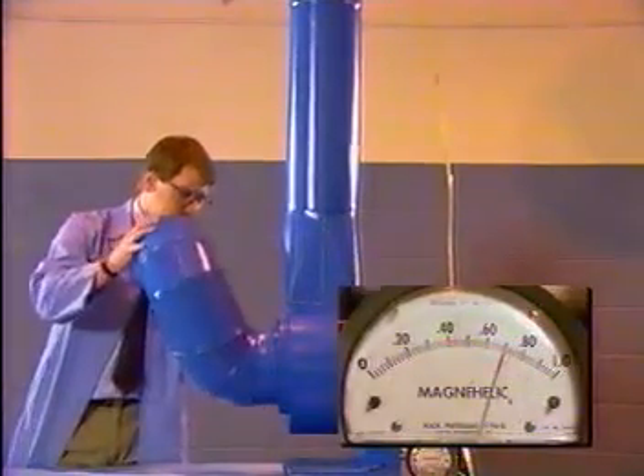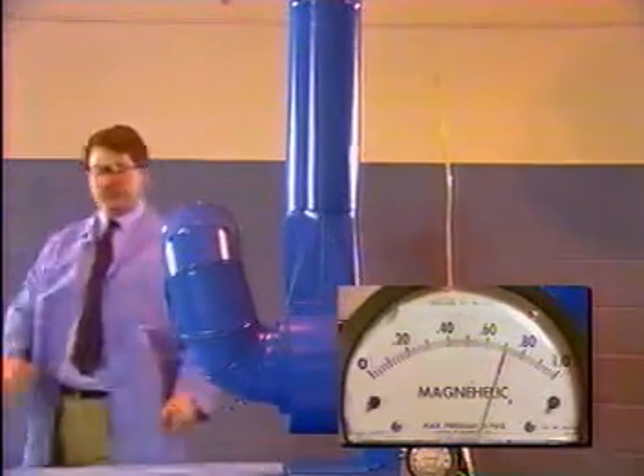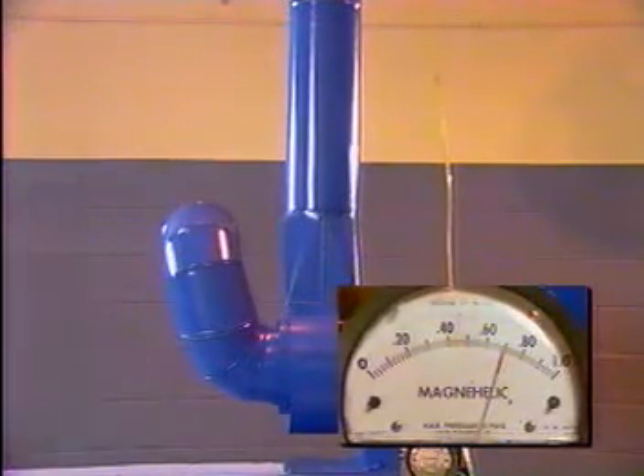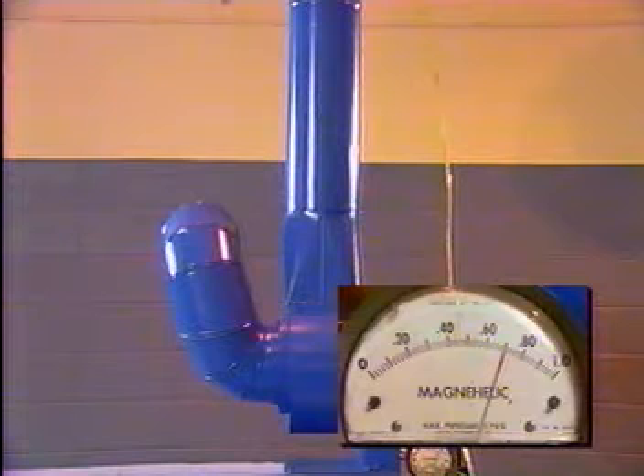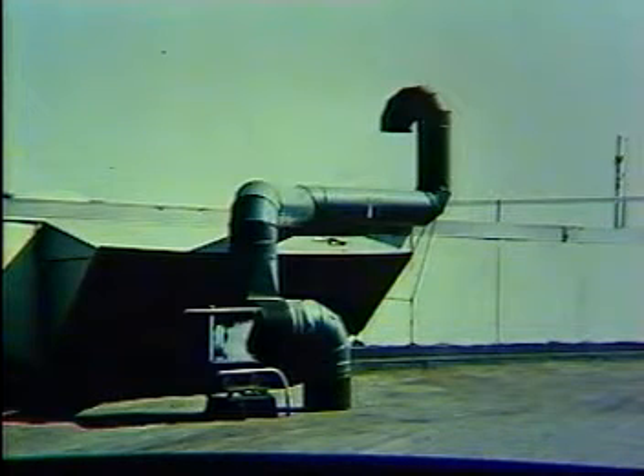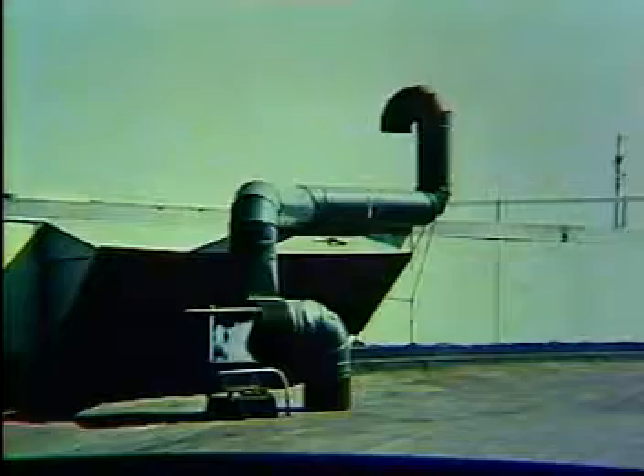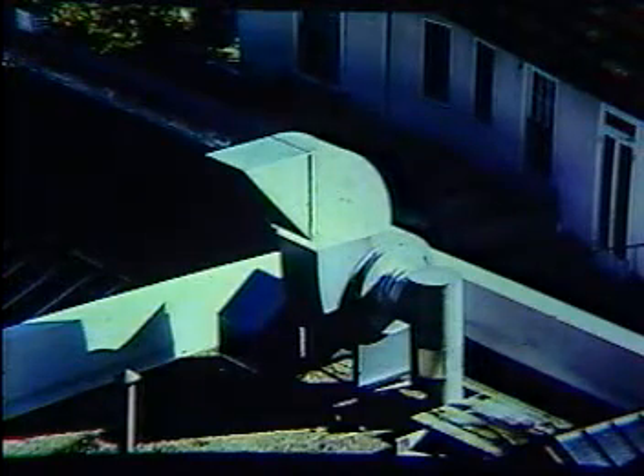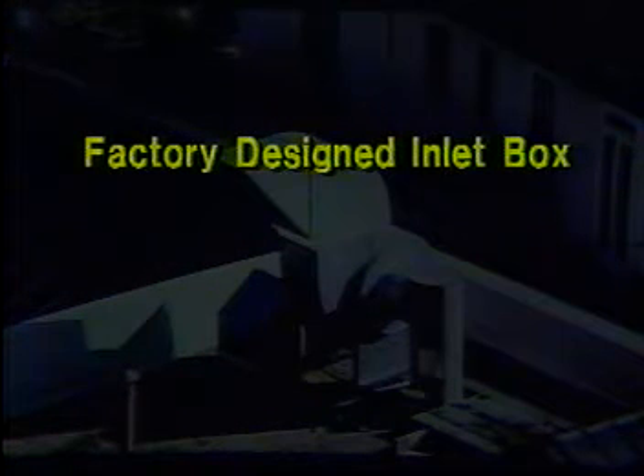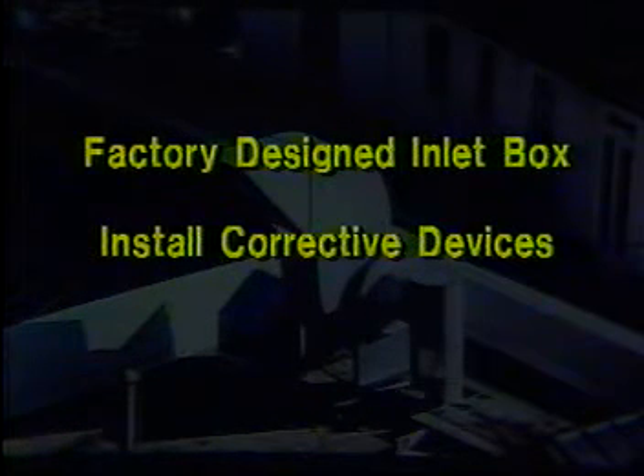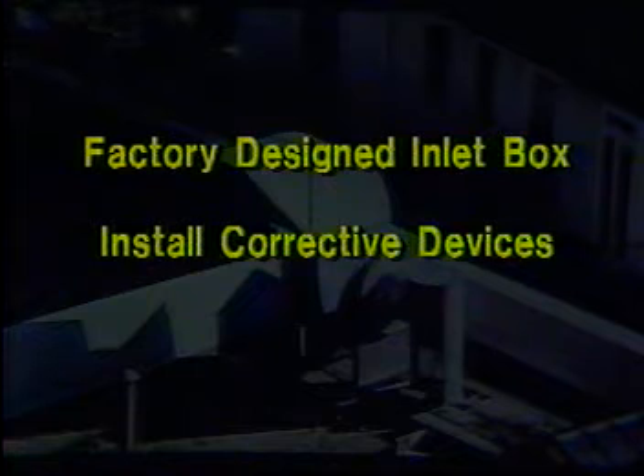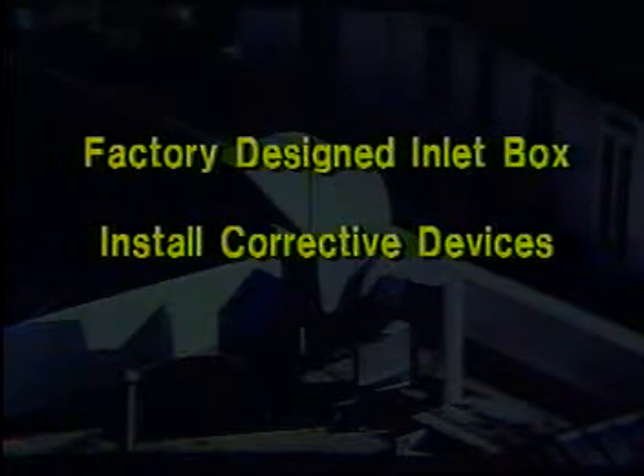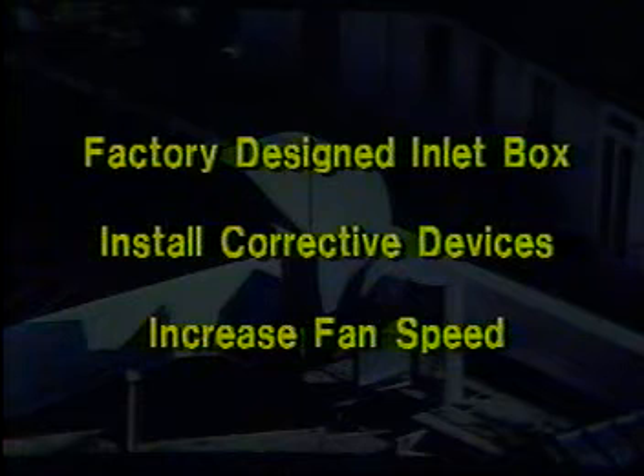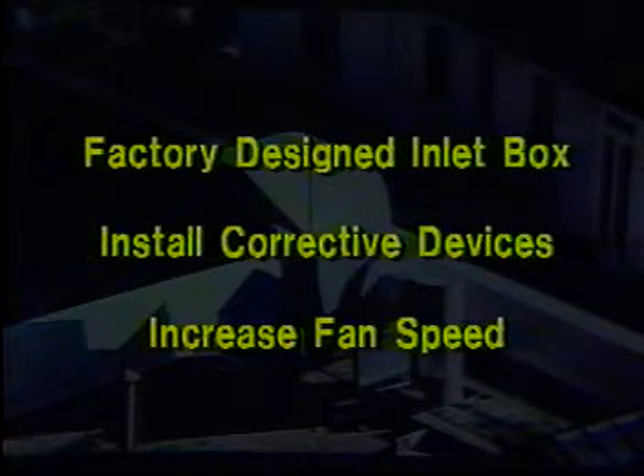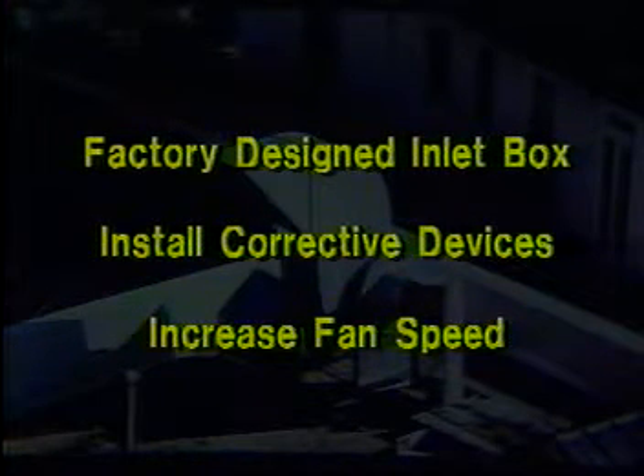The corkscrew effect created by two elbows positioned too closely together results in a performance drop of 0.3 of an inch of static pressure. Poor inlet connections produce losses in performance, but if space is a limiting factor, you have several alternatives. You can use a factory-designed inlet box and install corrective devices in the ducts, such as vanes, to minimize eccentric and spinning flow. Or you can increase the fan speed. But remember, with increased fan speed comes increased energy costs.